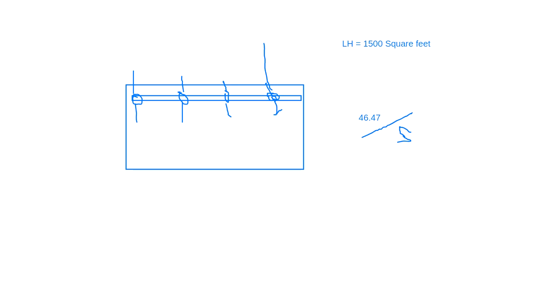So what NFPA wants to say is that when there is a fire going the rectangular way, there is a good chance that the fire will go into this area and all the sprinklers in the first branch line will activate. If the fire goes further down, it will break the second line in those areas and the third line in those areas.